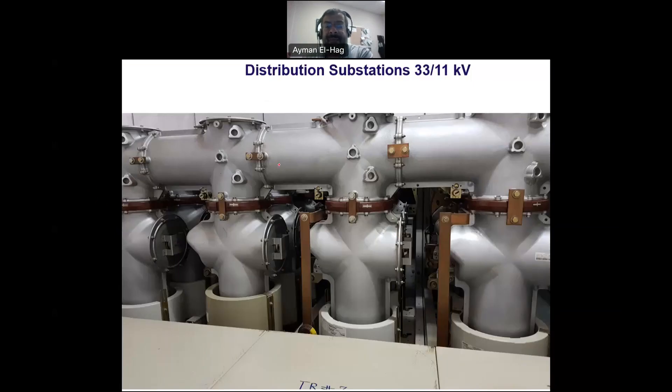Let's now have some physical photos of this circuit breaker. This is the 33 kilovolt GIS system, an SF6 type. We don't see the conductor because the conductors are basically inside this structure. To reduce the distance or the clearance inside the substation, we use a GIS system filled with SF6.